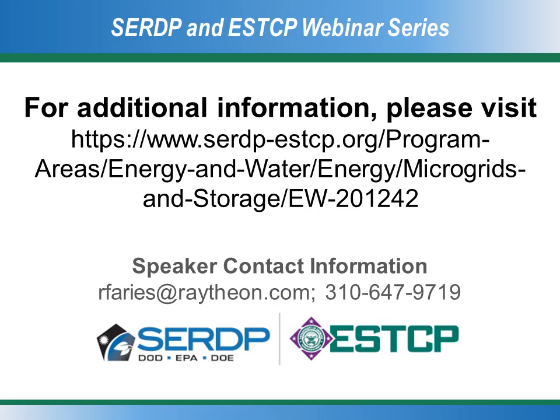Yeah, so a lot of the power analyzers that we used were Fluke brand power analyzers. They have their free power analyzer software for downloading the data, and you can also look at the output based on the settings of the power analyzer you were collecting with. We were using a Fluke 437 on the load data, collecting at quarter-second intervals, but the trigger points for some of the transient settings we were looking at were much quicker, sub-cycle type settings. That was collected with screenshots, and it was all analyzed using the Fluke software. It's free and available from their website.